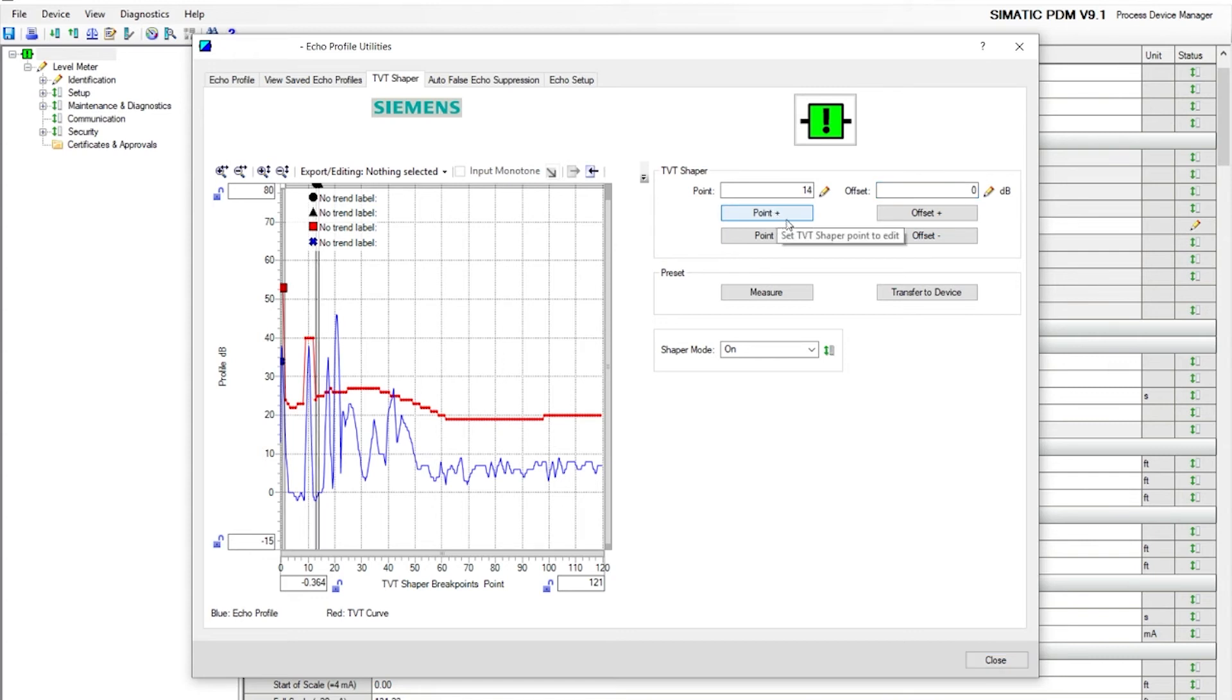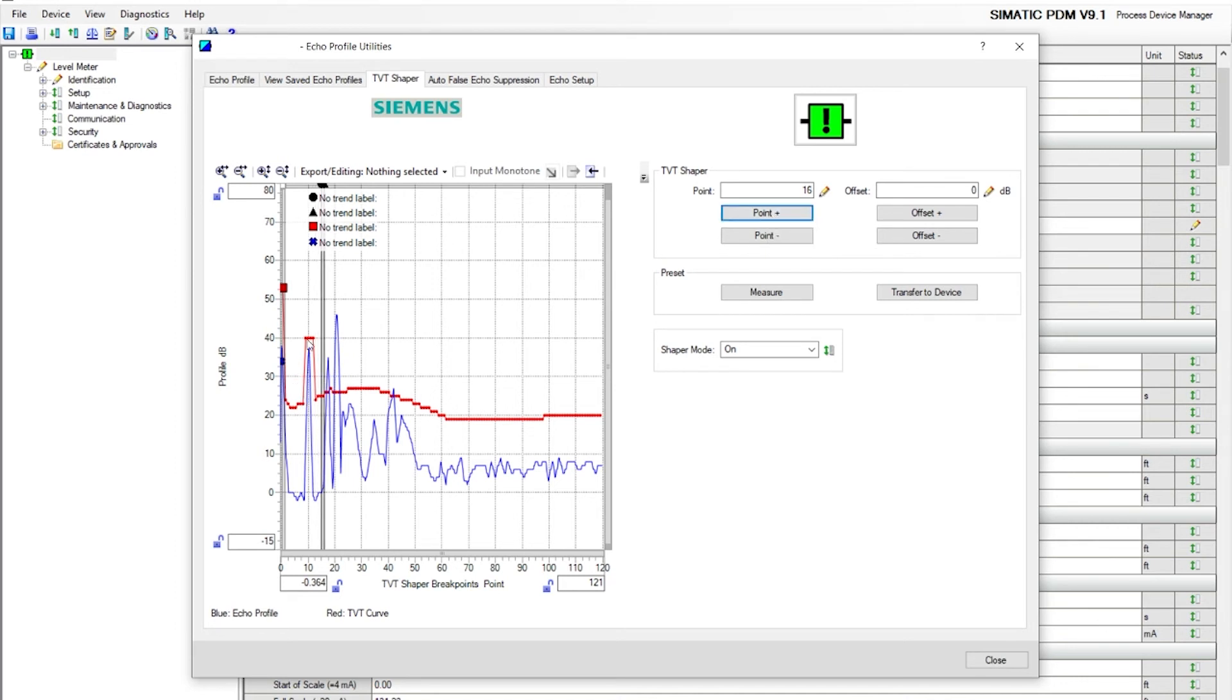There you go. You can see it will shift a couple of times. The red TVT raised right above the first false echo. Remember, anything below the TVT curve is ignored. Now let's go to the second echo.